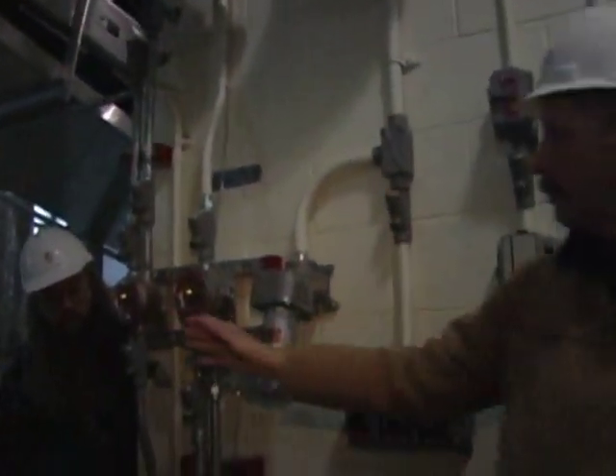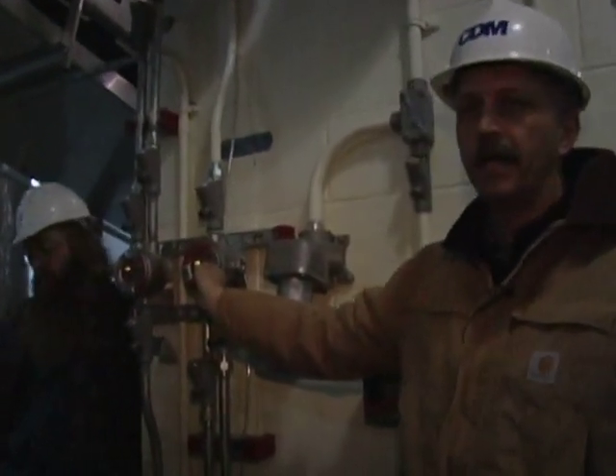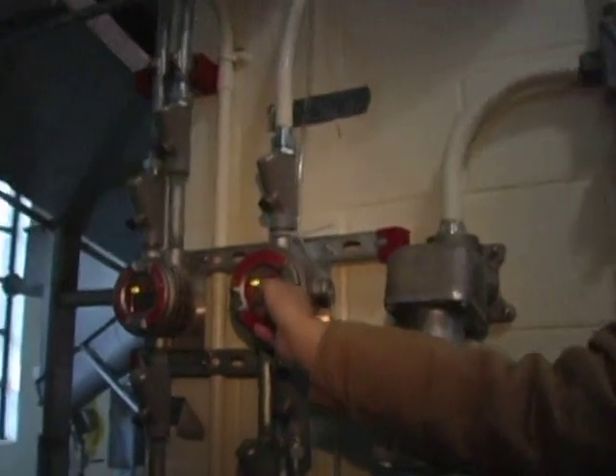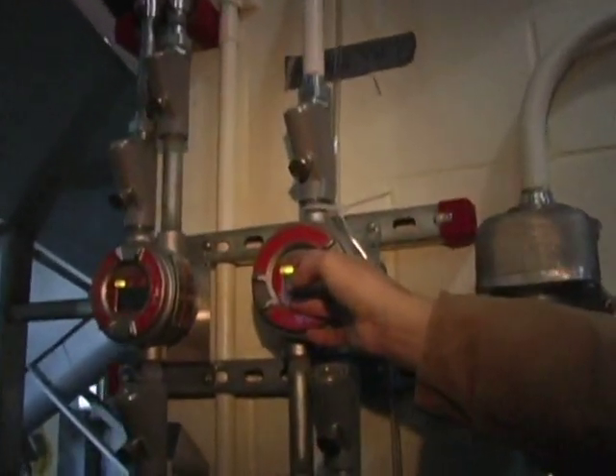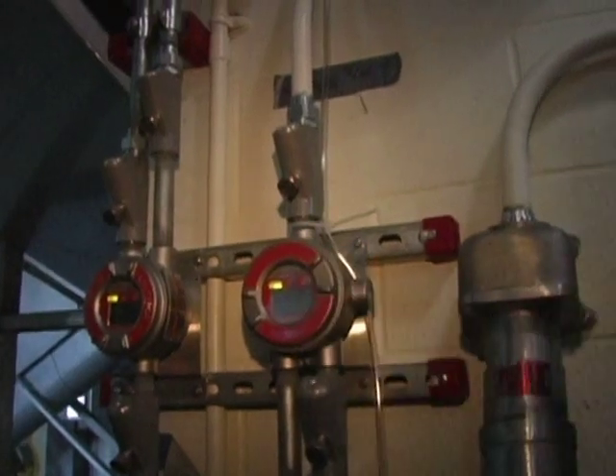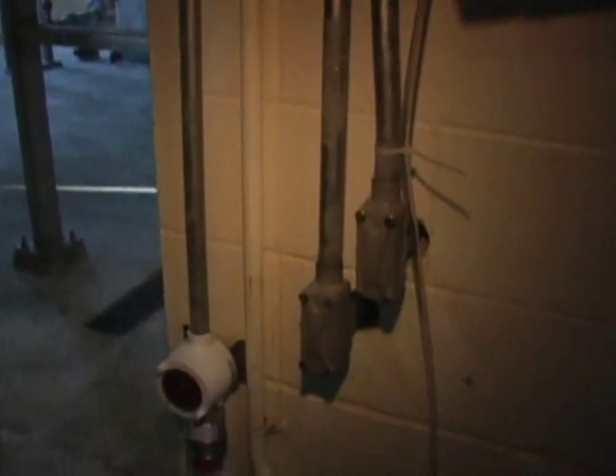From an equipment standpoint, you've got your hydrogen sulfide as well as lower explosive limit gas monitors. There's a set of two devices here in the room. The one that's directly overhead here is the lower explosive limit gas monitor. That will give you a reading here as well as back to SCADA. The hydrogen sulfide, which is a heavier gas that's going to hang near the floor, has the sensor near the floor here. And there are these two here, and there's also two of each of those within the other room, and I'll point those out as well.